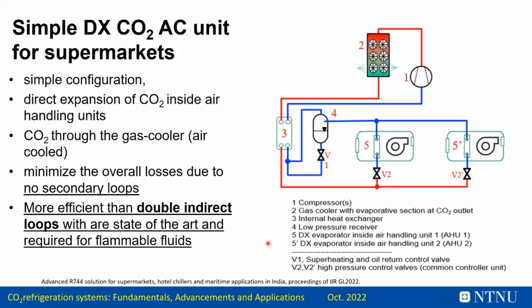If we cut out these indirect loops and go straight with CO2 to the gas cooler, rejecting the heat, and maybe even use some evaporative cooling at the last part of the gas cooler, we will be very energy efficient and very simple. And our investigation shows that this can be more energy efficient than a double loop, which is currently state of the art. We would love to introduce this in an example outside Europe.